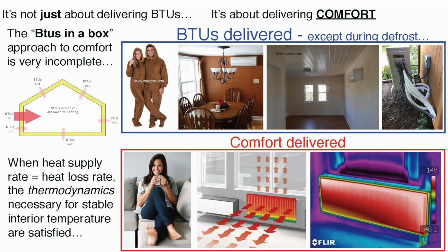I have this concept, we call it BTUs in a box. From a thermodynamic standpoint, to keep the box comfortable, all you have to do is inject BTUs in at the same rate that they're leaking out. You've got a balance there. So from the standpoint of thermodynamics, it doesn't matter how you deliver those BTUs. If it's 50,000 going out, it's 50,000 coming in, thermodynamics satisfied. But it's not about delivering BTUs. Our job is to deliver comfort.